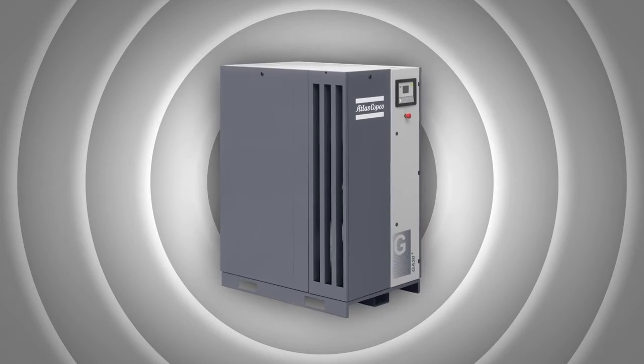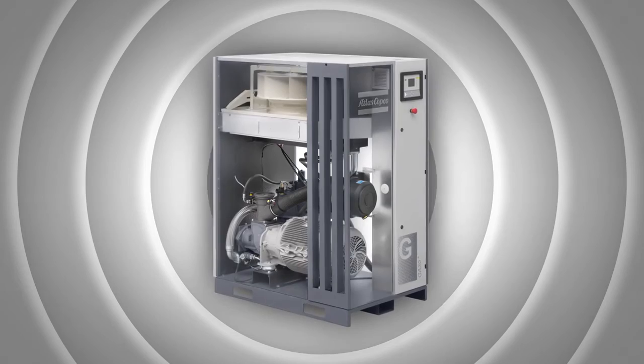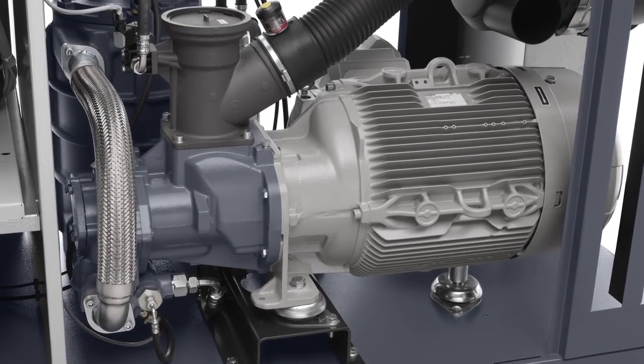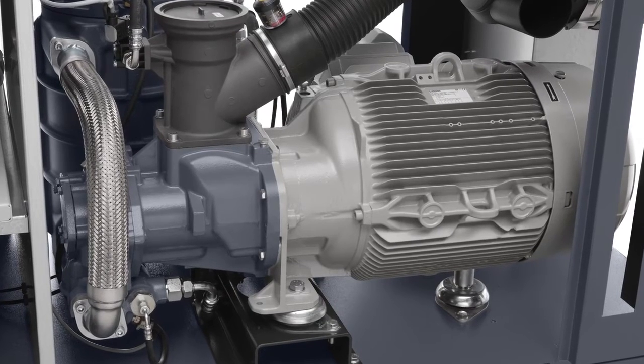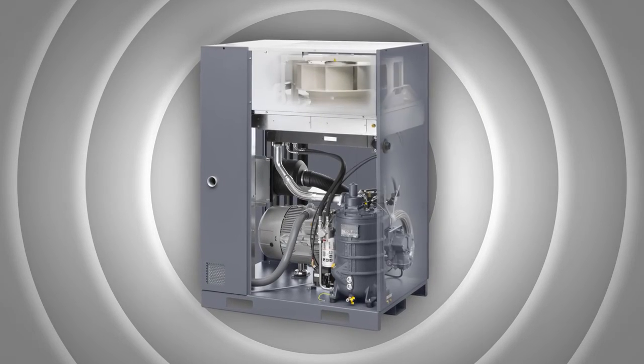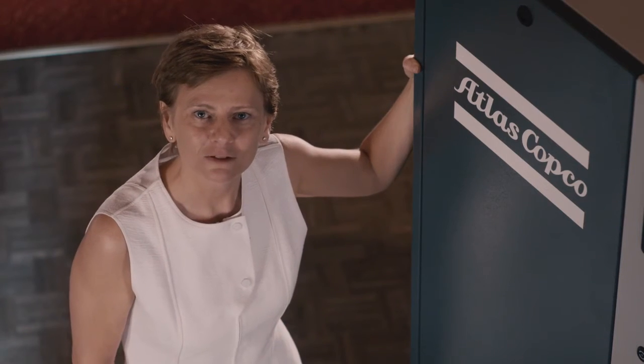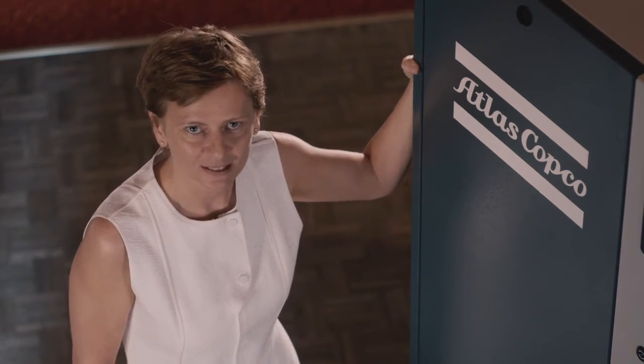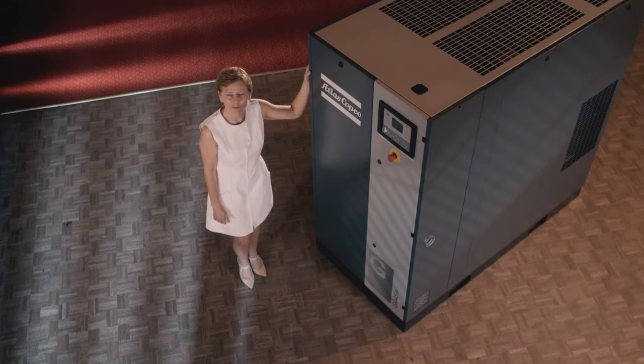There are a couple of surprises under the hood of this machine. The Leroy-Somer motor has been exchanged for a Siemens motor, which remains maintenance-free thanks to an oil-lubricated drive-side bearing and a greased-for-life non-drive-side bearing. We also designed a new and more compact oil separator vessel, optimized for the capacities of the C90 compressor element. The full feature version has its own dedicated layout, canopy, and frame size. We rearranged the dryer layout to minimize the footprint.